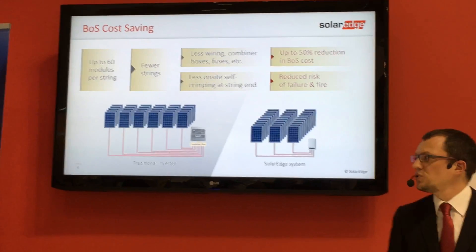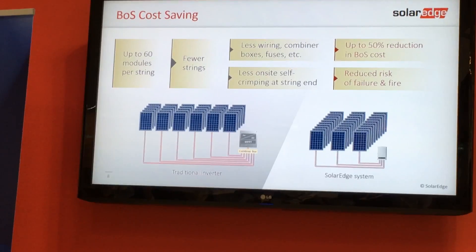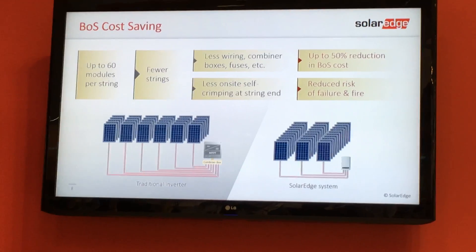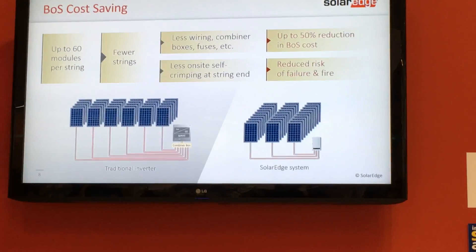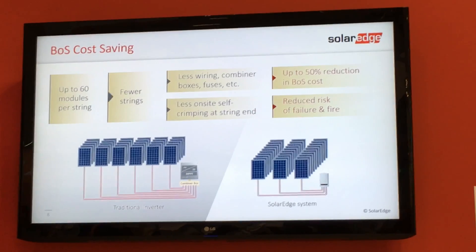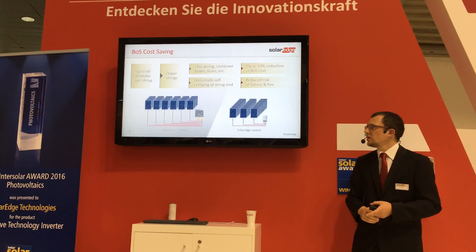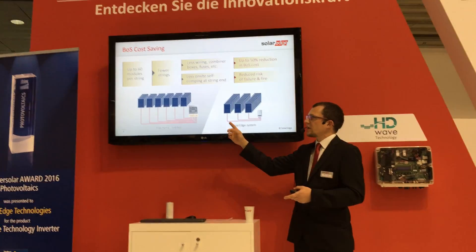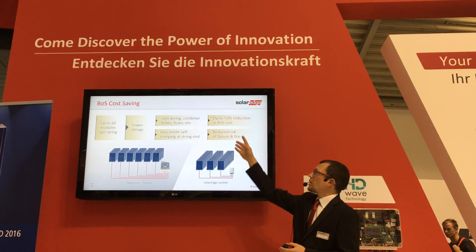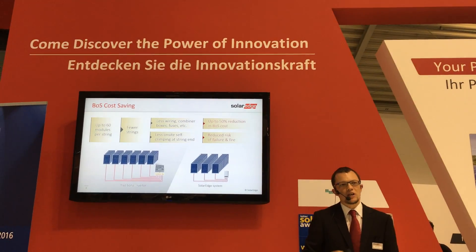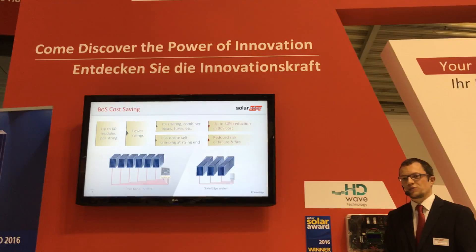There are lots of strings here running between the modules and the inverter. In some cases, you need the combiner boxes. With our optimized solution here, you can put up to 11.25 kilowatts of module power in one string. So in many cases, this allows you to severely reduce the number of strings that you need to run here, allowing you to save on the cabling and also on the combiner boxes. In some cases, you can reach up to 50% reduction in the balance of system costs due to the lower cabling and combiner boxes.